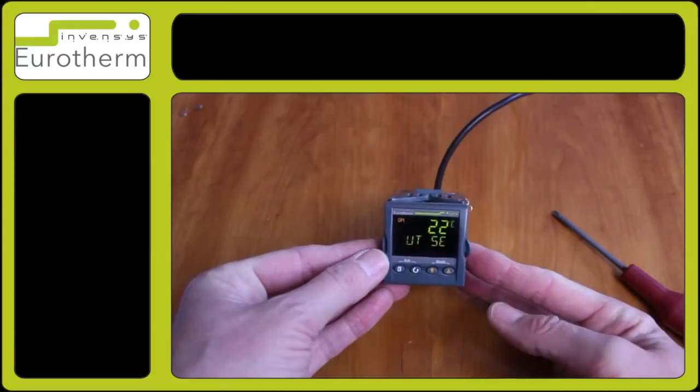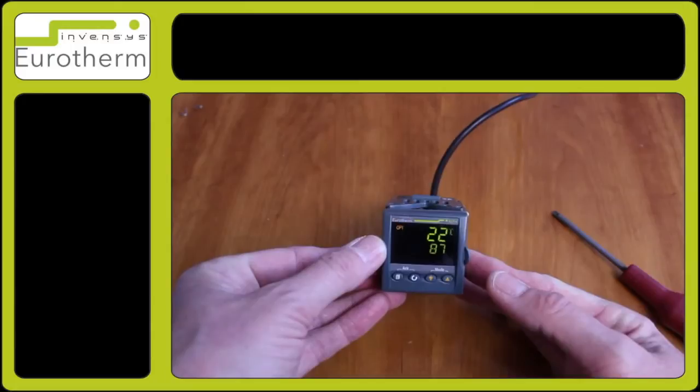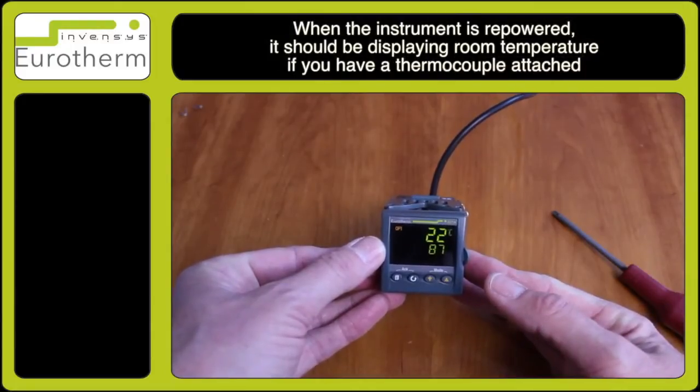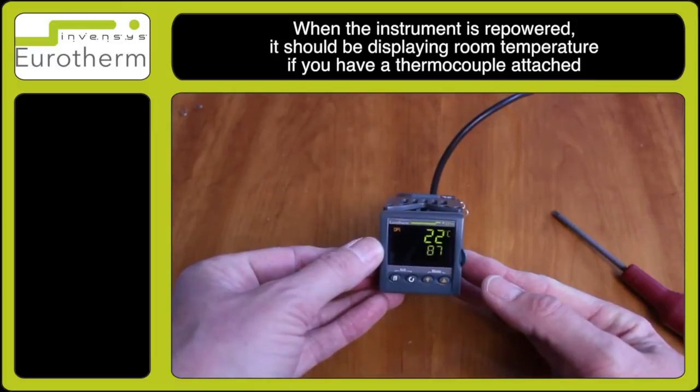Wait for the instrument to repower and observe the top display, the temperature display. This should now be showing room temperature if you've had a thermocouple connected to the unit.